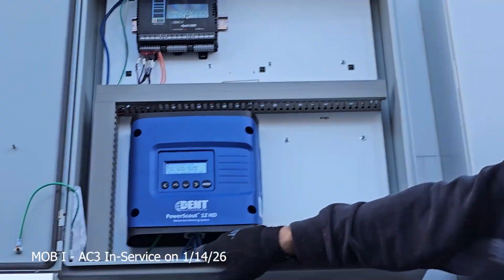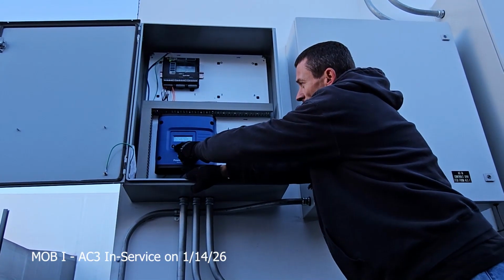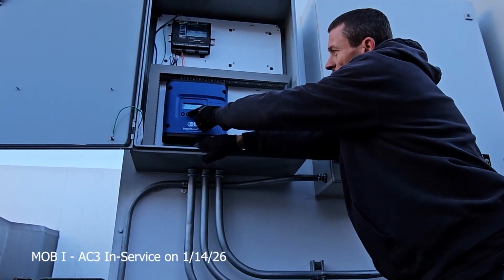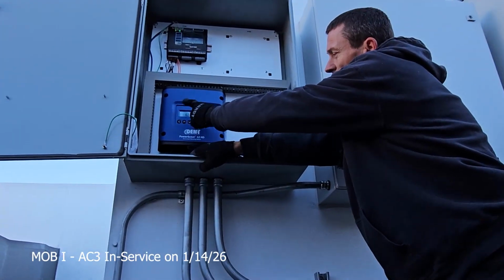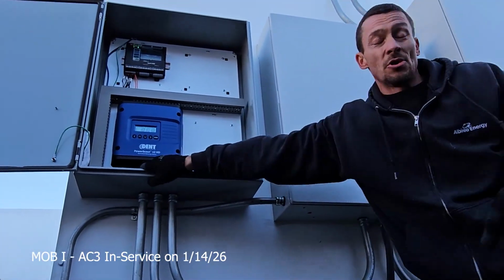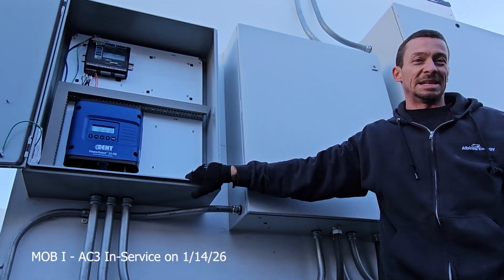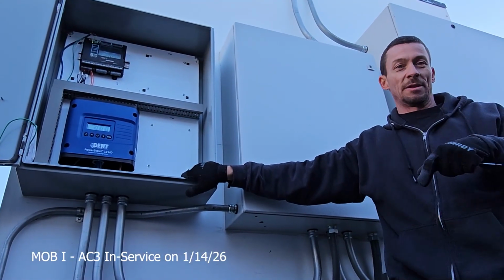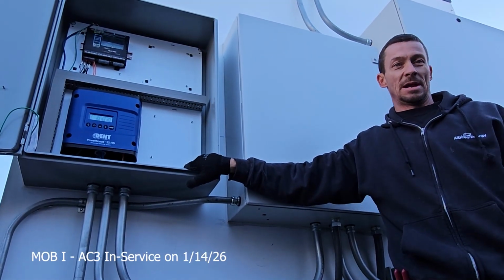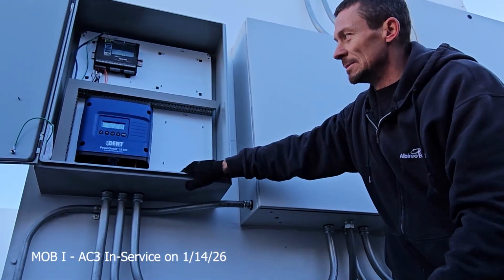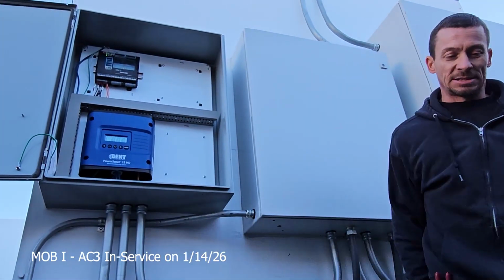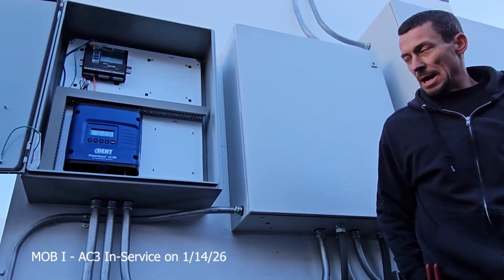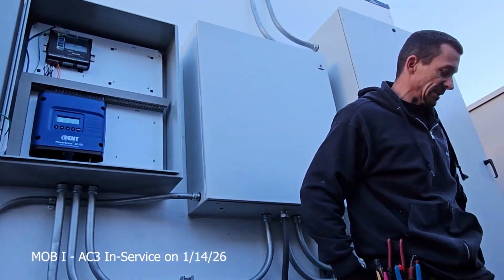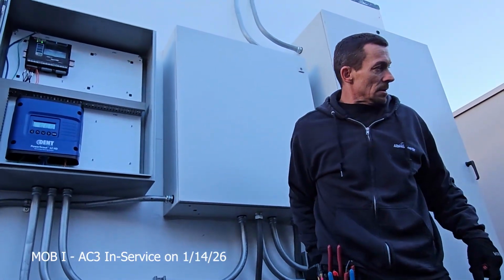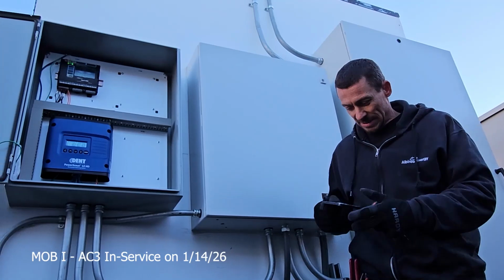Like I said, if you really want to, you can see real-time values right here. The only problem with that is it just says element A, B and C, and you're not going to know what it is without going to the front end and looking. It'll tell you supply fan on the front end. I know A is probably supply fan, B is usually the exhaust or the return, and C is the total power. That's what's in here. But like I said, I don't think you guys ever even look at this stuff.